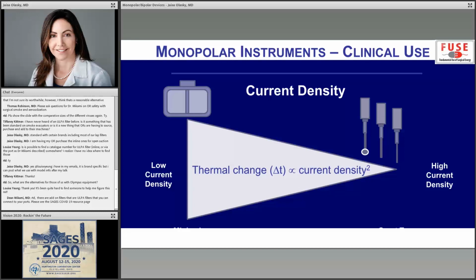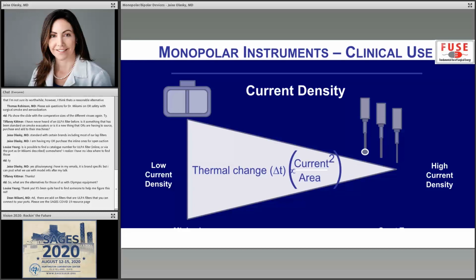So this is important to know when you're trying to have a different tissue effect, that you might just need to turn your monopolar instrument in a different direction if you're using the hook and you're just using the tip of it, versus using the elbow of it. Or maybe you need to switch to the spatula in order to have a larger tissue contact area. And so again, we see here our current squared over area is giving us that current density, and that's affecting our thermal change.